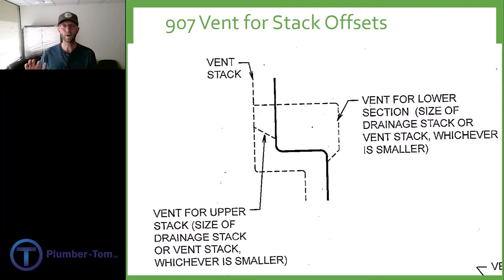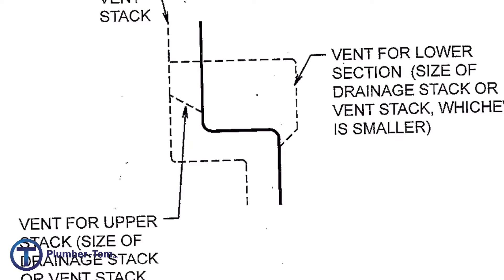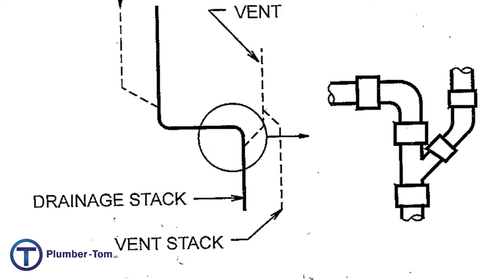In section 907, we look at vents for stack offsets. It says if there are five or more branch intervals above that offset, we need to provide some venting so that as fluid comes down through that offset, it has enough air to flow. We would need to provide a vent on the upper end of that offset and on the lower end. You can see how this branches off around that offset and ties back over into the vent stack. Here's an example of how we might branch off on the lower end of this horizontal offset — also known as a yoke vent — where it's intended to provide airflow into the lower end of that offset. You can just branch off with a Y before that offset 90 and send that vent over to the vent stack.